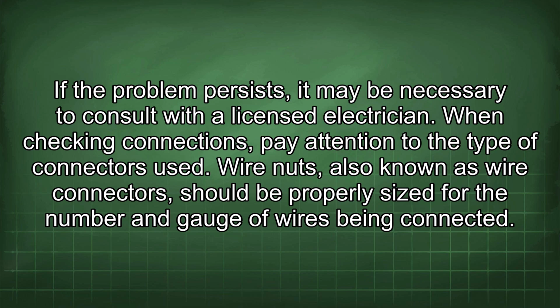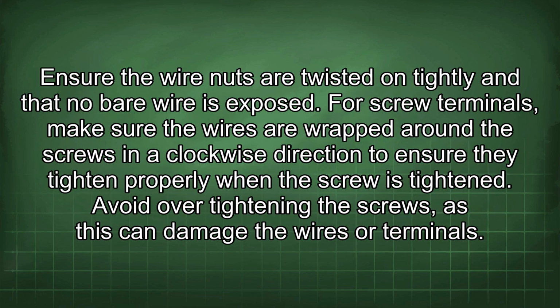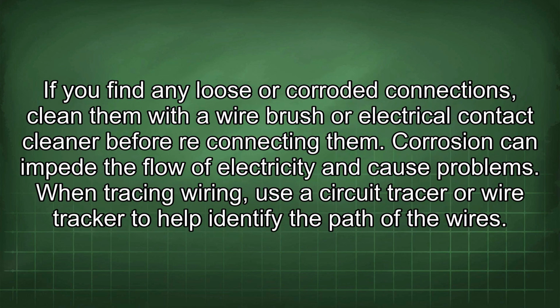When checking connections, pay attention to the type of connectors used. Wire nuts, also known as wire connectors, should be properly sized for the number and gauge of wires being connected. Ensure the wire nuts are twisted on tightly and that no bare wire is exposed. For screw terminals, make sure the wires are wrapped around the screws in a clockwise direction to ensure they tighten properly when the screw is tightened. Avoid over-tightening the screws, as this can damage the wires or terminals. If you find any loose or corroded connections, clean them with a wire brush or electrical contact cleaner before reconnecting them. Corrosion can impede the flow of electricity and cause problems.